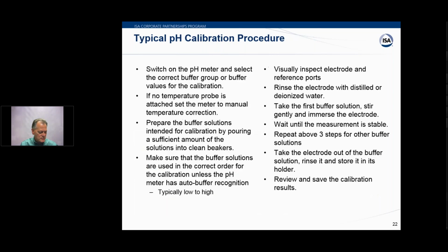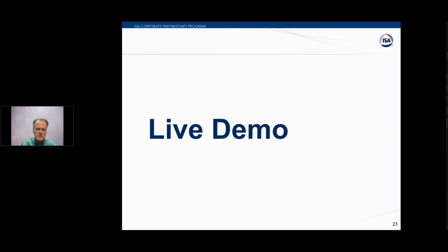So on the next slide, we have some procedural information, and I'm not going to go through every one of these, but we thought it would be good to leave you with this information where you can maybe incorporate some of these ideas into your procedure. The second bullet there is mentioning this temperature probe. Again, make sure that you address temperature correction when you're doing calibration. And then over on the right, at the top there, it says visually inspect electrode and reference ports. That's always good practice to see if there might be something that you do need to clean or correct. And as you're moving through the buffer solutions, you're going to see Roy rinse the probe off with distilled water. So that's also good practice. So I think that's just a little bit of insight on tips for calibration, but now Roy gets to show you how to do it.